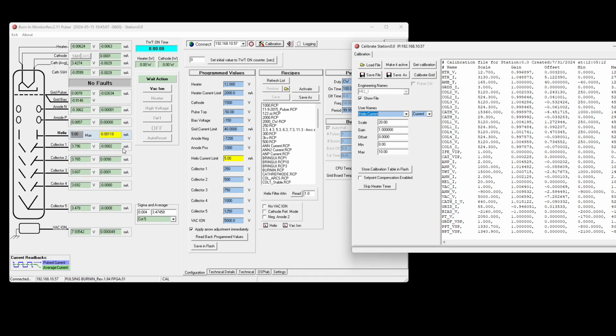So first thing we're going to do is go over to the unit and set up our voltage measurement on the multimeter, and we're also going to ground the cathode. The reason we ground the cathode is, one, for safety, and two, it also stabilizes the measurements of the bias and pulse top voltages so that there's not a lot of drift and we can calculate our gain and offset accordingly. So I'll be right back.